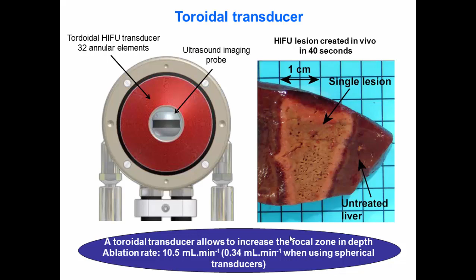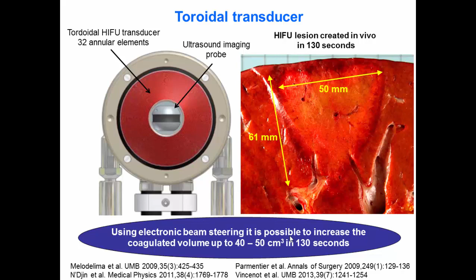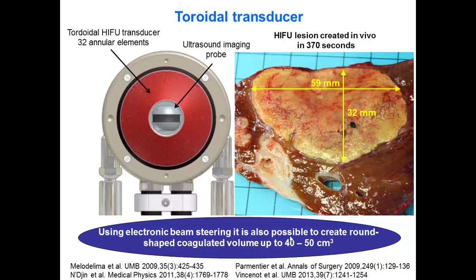If we perform electronic beam steering during treatment, we can even enlarge the ablation zone up to 40 to 50 cubic centimeters in only 2 minutes and 10 seconds of treatment. And according to the beam steering we use, we can also ablate a round-shaped region of the liver, which is a volume similar to a tumor.